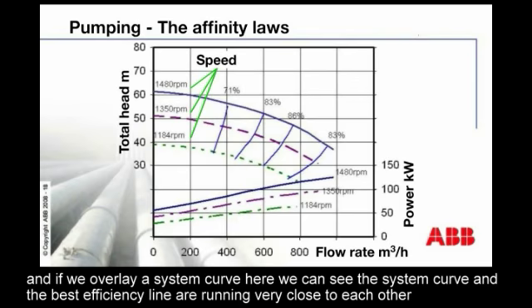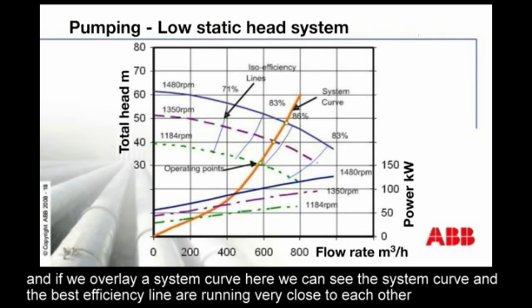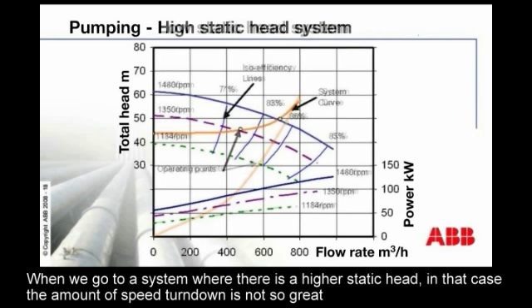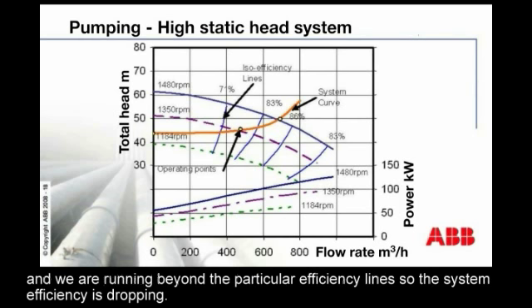If we overlay a system curve here, we can see the system curve and the best efficiency line are running very close to each other on a system where there is a low static head. When we go to a system where there is a higher static head, the amount of speed turned down is not so great, and we are running beyond the particular efficiency lines, so the system efficiency is dropping.